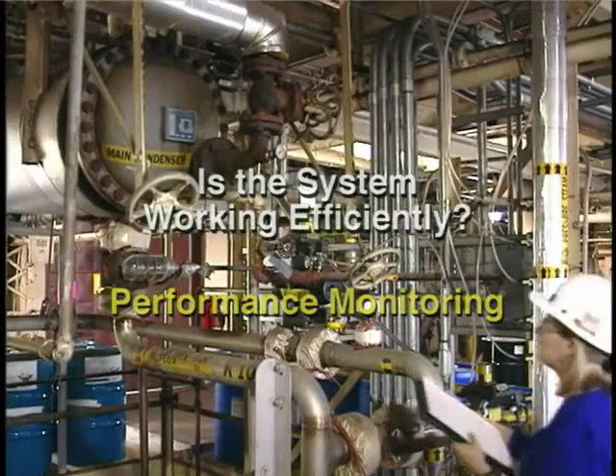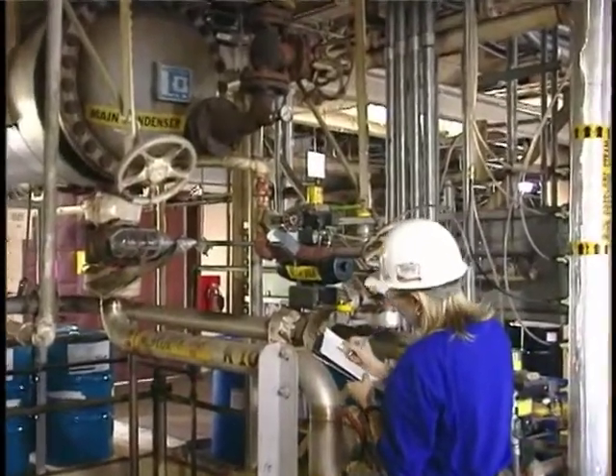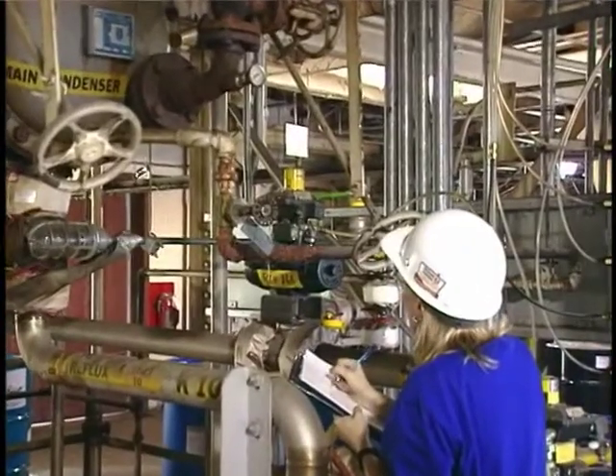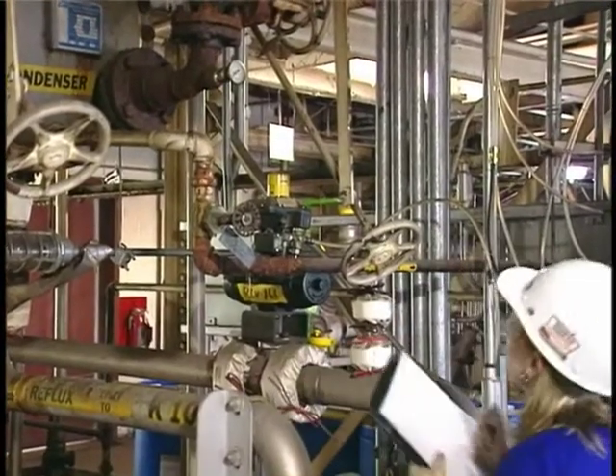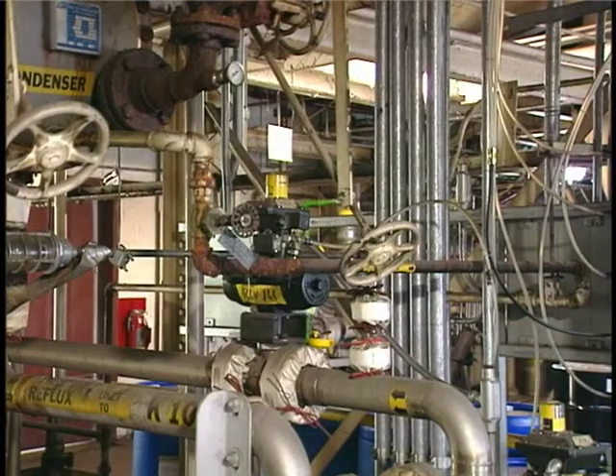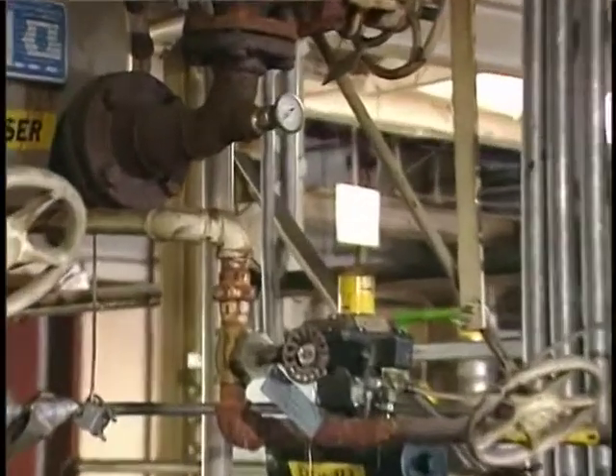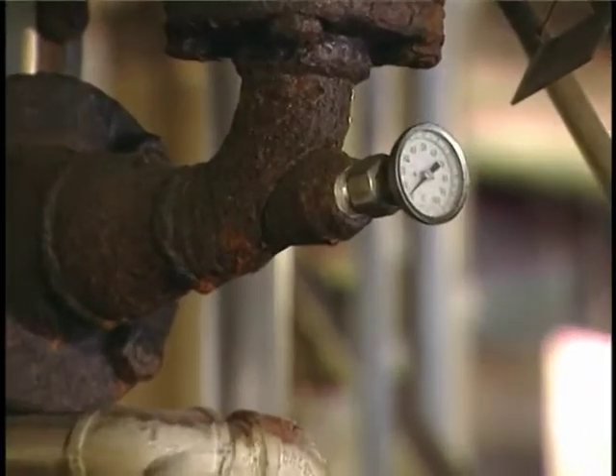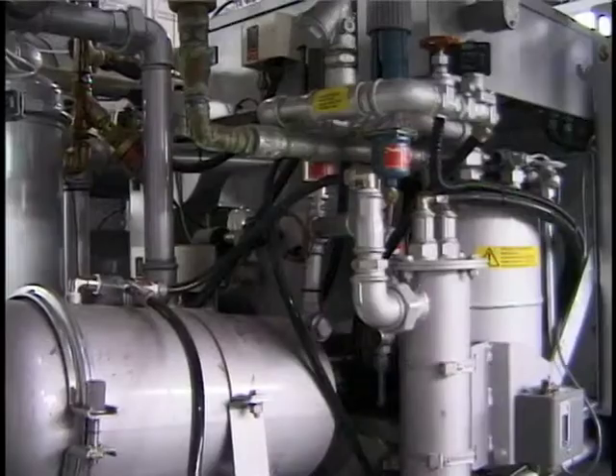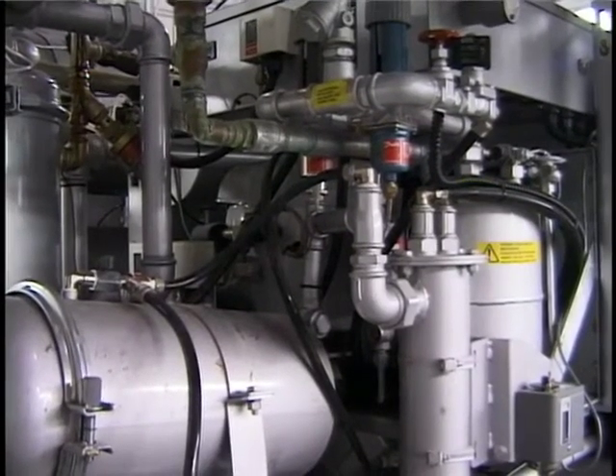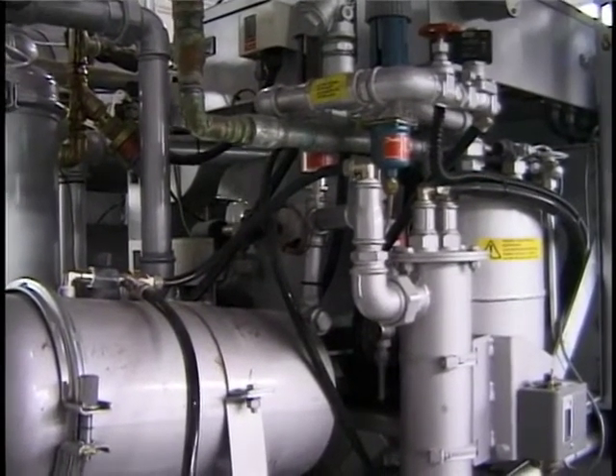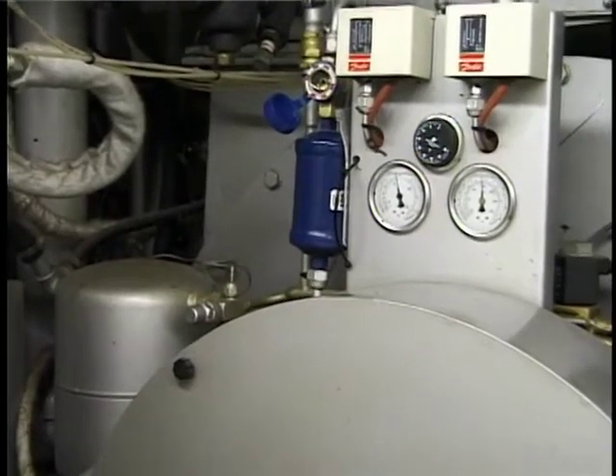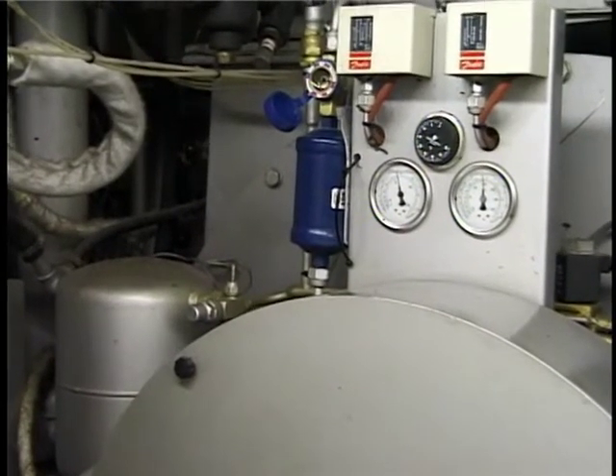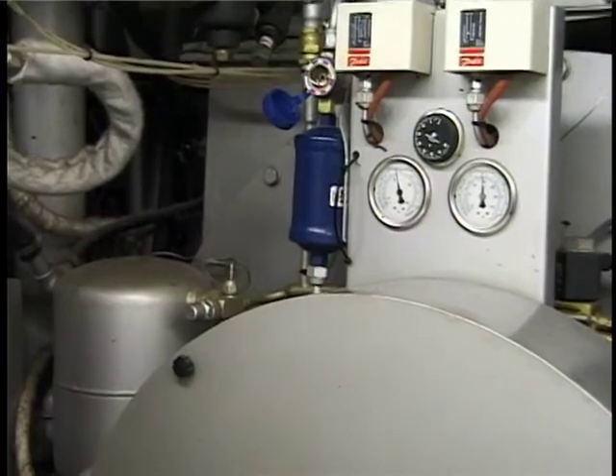The ability to evaluate performance problems during a field inspection will depend on how well the system is instrumented. Most refrigeration systems and complex cryogenic systems will have sufficient instrumentation for an adequate evaluation. However, simpler systems may have limited instrumentation. Performance evaluation of these systems will be difficult unless measurements of important parameters are made.